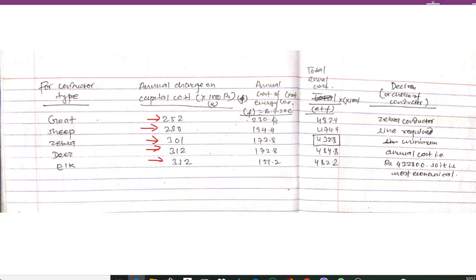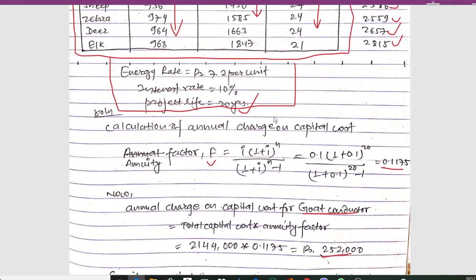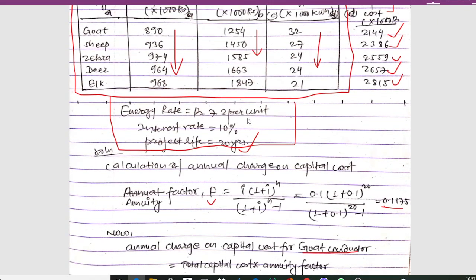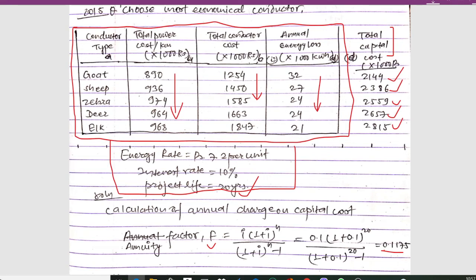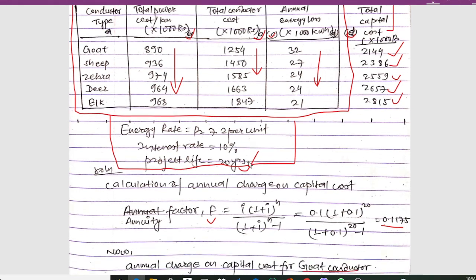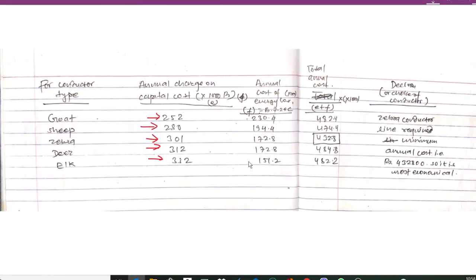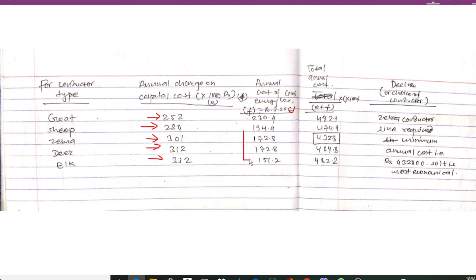Now for the annual cost of energy loss. Using the energy rate of 7.2, and denoting the columns as A, B, C, and D respectively — the annual cost of energy loss equals 7.2 multiplied by column C. For Goat conductor we get 230.4, and for Sheep we get 194.4. Similarly, the respective values are calculated for the other conductors.